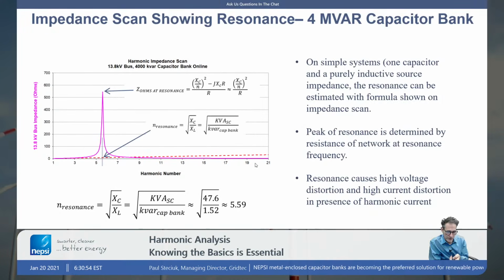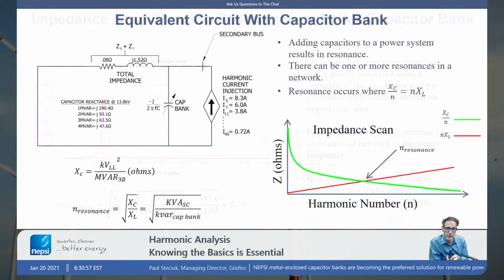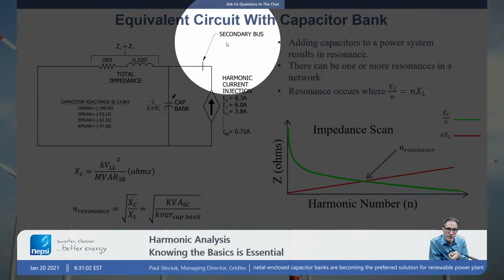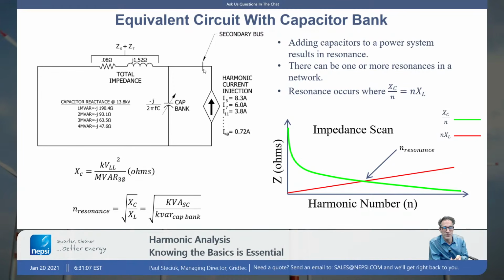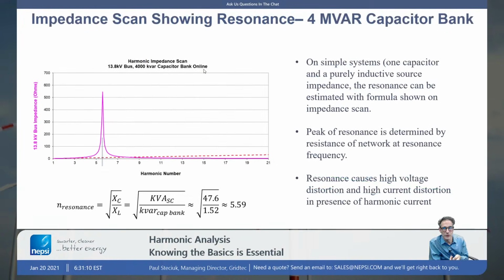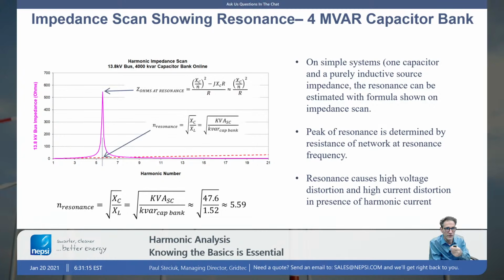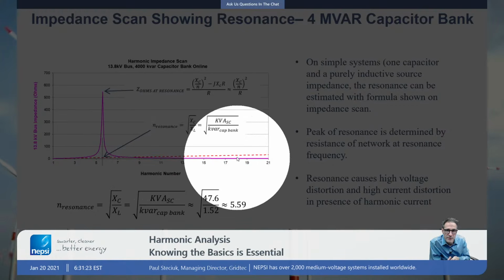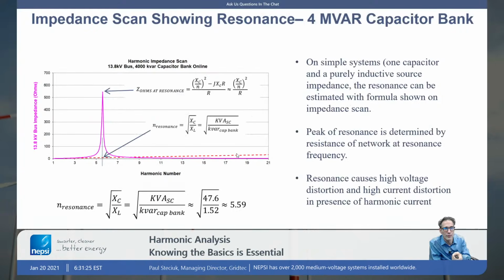If we were to draw the impedance curve, though, and say look into the circuit here, we've got the secondary bus. We look into the circuit. What impedance does that harmonic current injection see? Well, that's shown here with that magenta curve. The magenta curve is the impedance, the driving point impedance as it's referred to. So here you can see what has happened. We have that red dashed line here. That's that original transformer impedance line, the source impedance line. That's the starting point of this analysis.